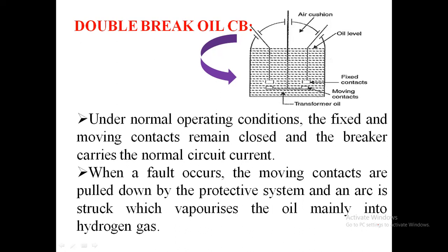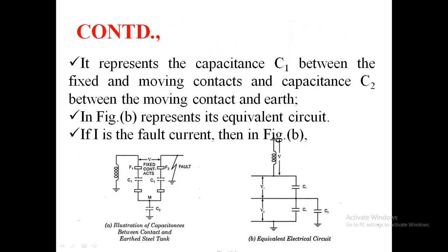With the fast moving contact speed, there will be an unequal voltage distribution across the breaks. One may take 70 to 80% of the interrupting duty. So, as represented here, when a breaker interrupts an earth fault, the recovery voltage will not be divided equally between the two breaks.